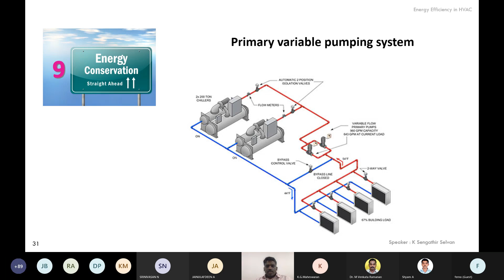Okay, so how are these related to annual energy costs? Having a different type of chiller or different type of pumping does not change the load, because all these things are on the generation side. So we don't have to compare the capacity reduction, but we have to compare the annual energy cost reduction here. So we saw that energy conservation measure 4 was reducing by 55%. Now energy conservation measure 5 is changing the air cooled chiller to a water cooled chiller. So we have another 10% reduction overall. Though there is a reduction in chiller power consumption by 40%, overall it is 10% only.